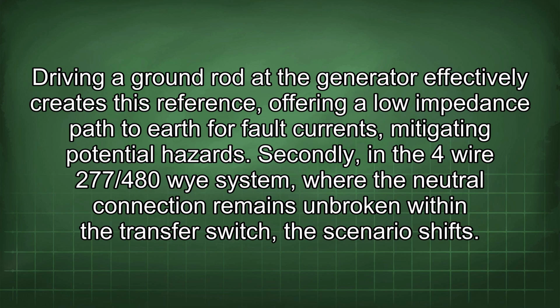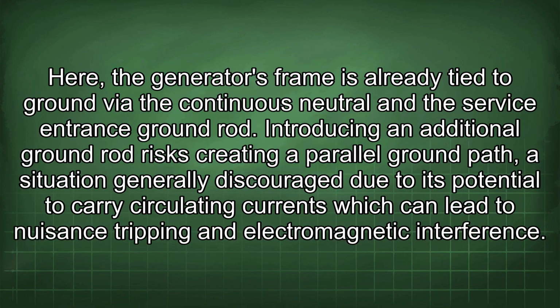Secondly, in the 4-wire 277/480Y system, where the neutral connection remains unbroken within the transfer switch, the scenario shifts. Here, the generator's frame is already tied to ground via the continuous neutral and the service entrance ground rod. Introducing an additional ground rod risks creating a parallel ground path, a situation generally discouraged due to its potential to carry circulating currents which can lead to nuisance tripping and electromagnetic interference.